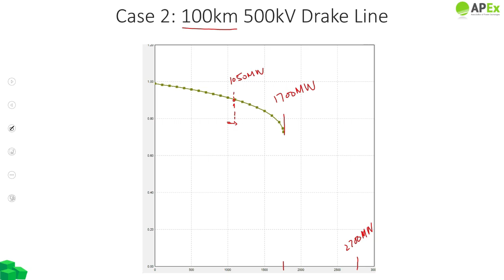So when our system is operating at 1050 megawatts, our voltage stability band or stability margin would be this. However, in any case, we will have to limit our power according to the grid code before this line. So essentially, we can safely transmit our power at around 1050.